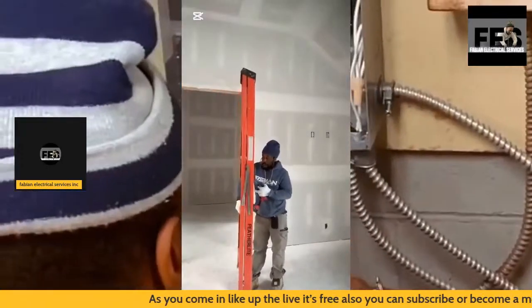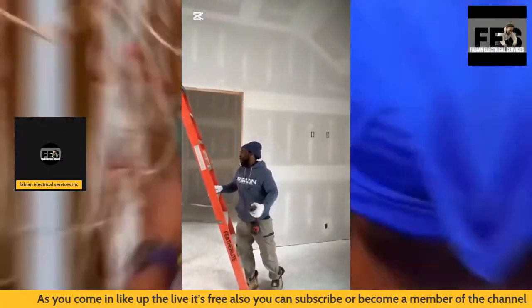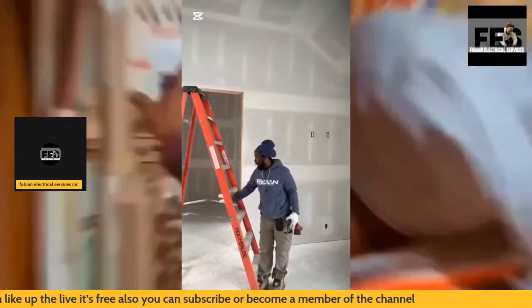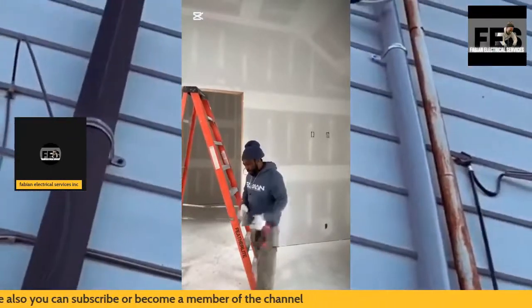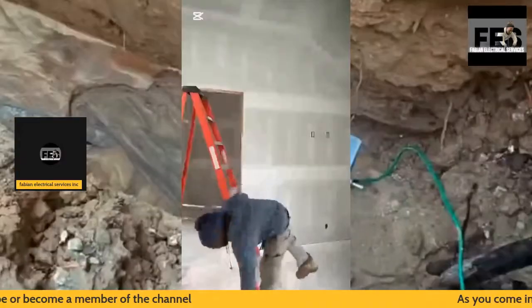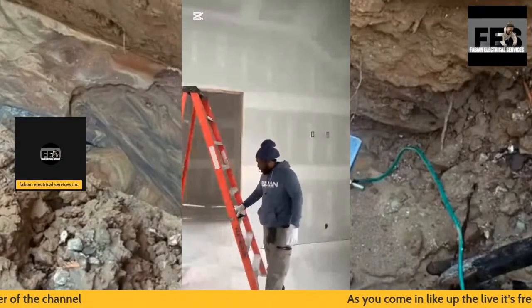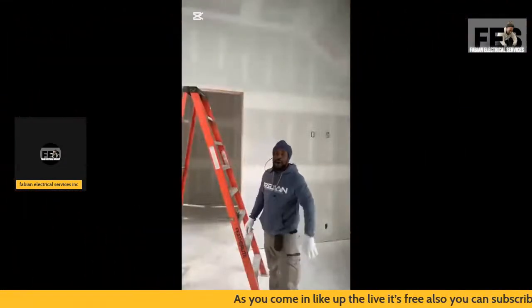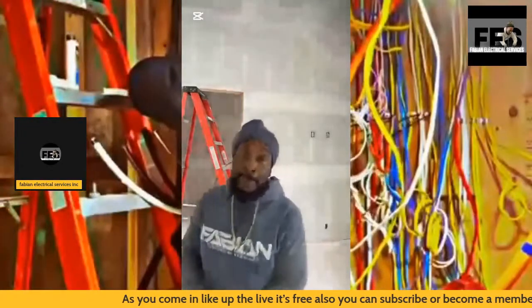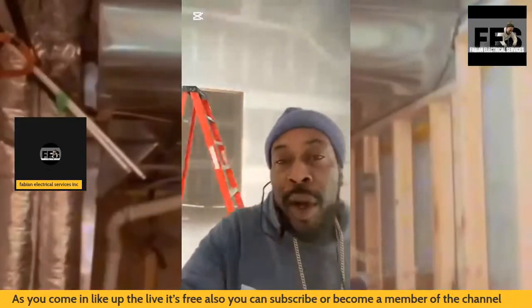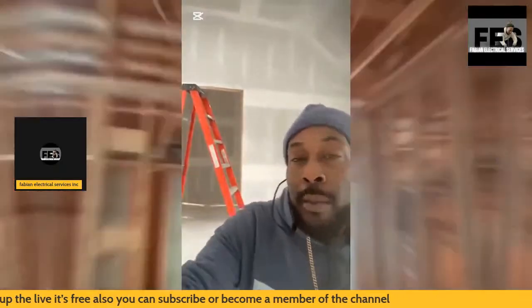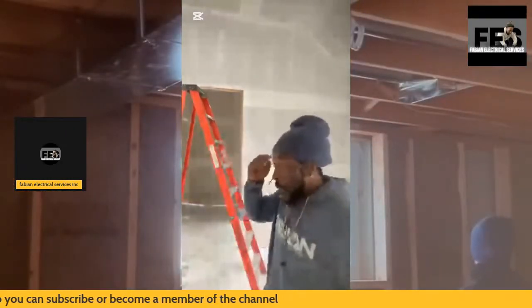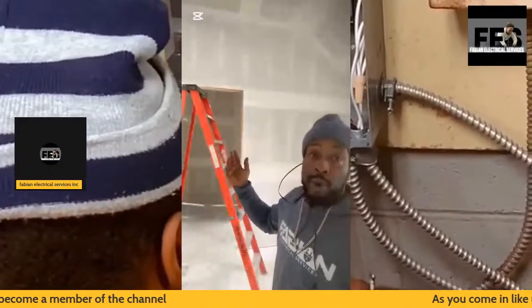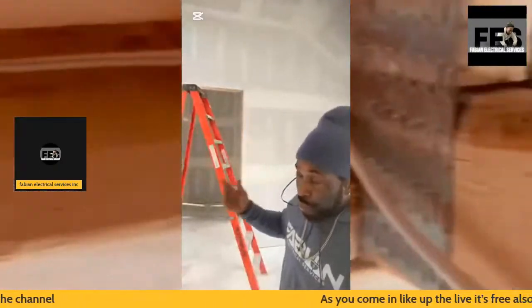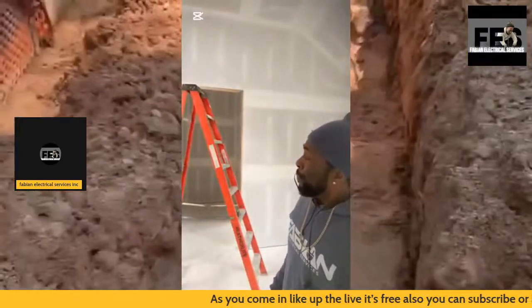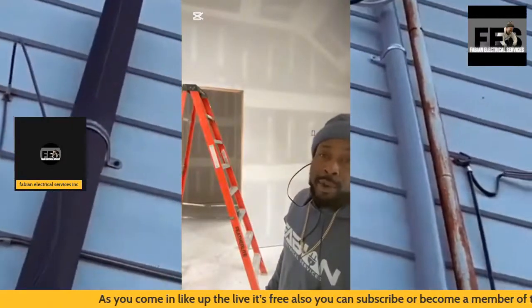Again, this is how I like to do my installation. It's very important that the electrical installation is up to code. Also, when it comes to our smoke detectors, we have to make sure that we maintain power from the lighting system. Very important: the power for all smoke detectors in Canada is picked up from your lighting circuit, it doesn't come from anything else.